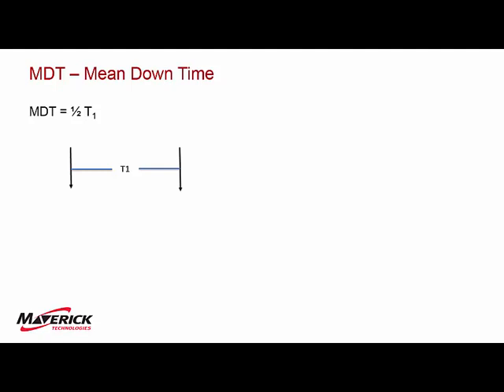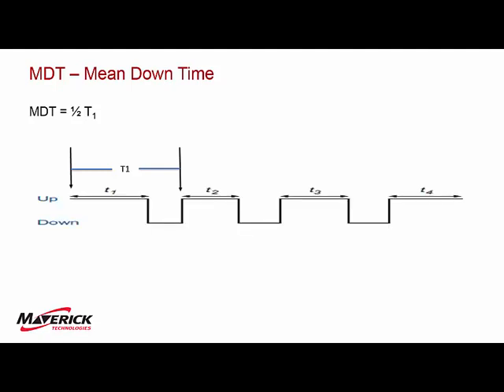So undetected failures are failures that you don't know happened. It's that level transmitter that's stuck, and when the level goes high, your tank's going to overflow because it's still stuck, but you don't know it until it happens. So that's going to lengthen these things. Going into this mean downtime, mean downtime winds up being half, on average, half of the time between when you test something. If you look at these failures again and you imagine the scenario: I install it, everything's running great, life's good, it breaks. But I don't know it broke. And then I either test it or I need it. But in this case, I test it and I find the test. On average, it's just as likely that it's going to fail at the beginning than in the end. There's a constant probability of failure. So you can use half of your proof test time or your test time to give you this mean downtime.